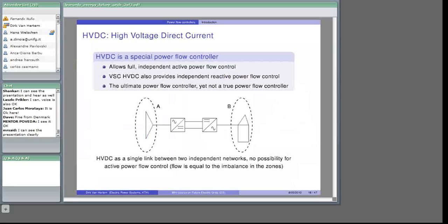The VSC HVDC also allows independent reactive power flow control at both ends. As such, I think the HVDC line is an ultimate power flow controller, but maybe not a very true power flow controller. Just to see it as an example, if you have two systems with only one HVDC line in between, then it's not really a power flow controlling device, because the device can only take care of the imbalance between the two.